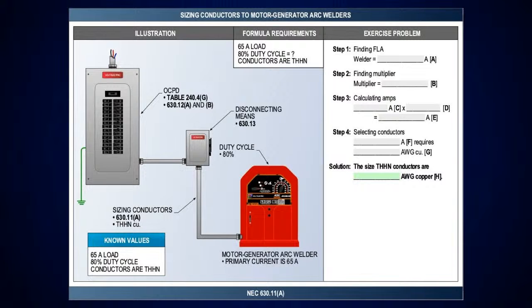You got a motor generator. We got a 65 amp load and 80% duty cycle. So step 1, 65 amps. Step 2, look at table 630.11, get the 80% there, come across, find out what the multiplier is, calculate it, and size your conductor. Okay?